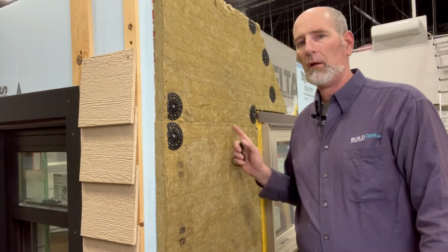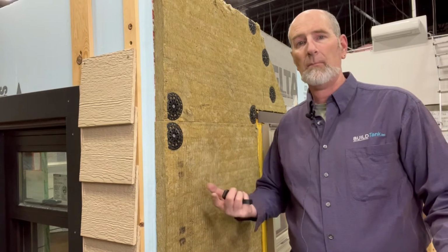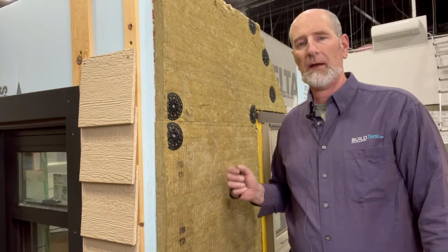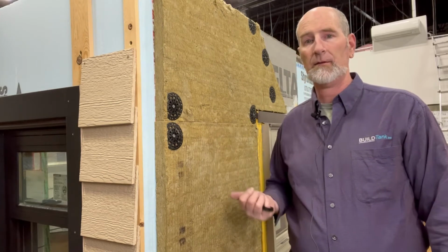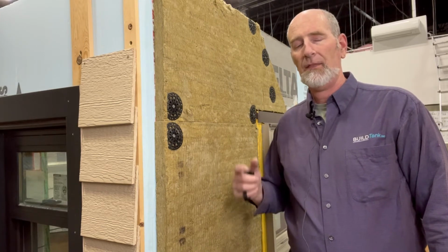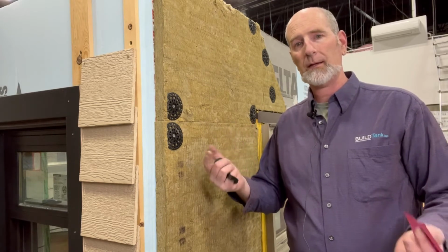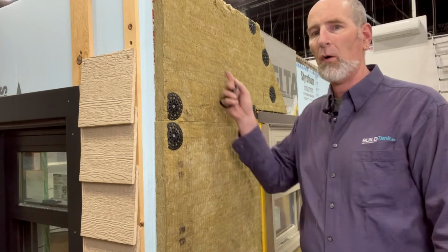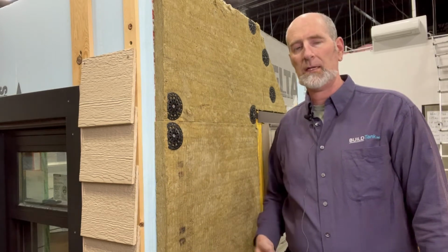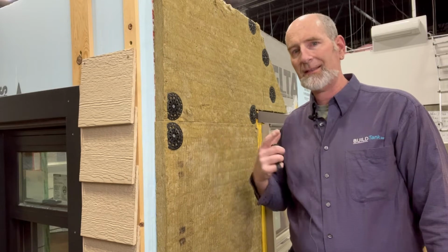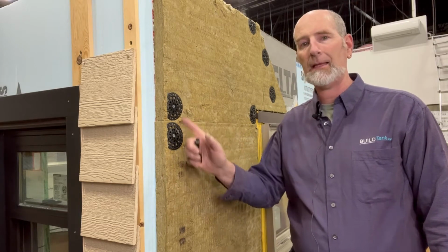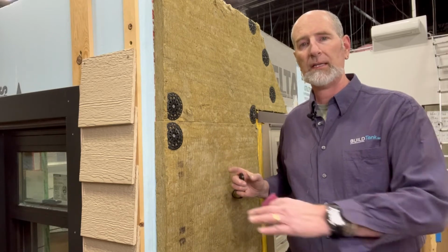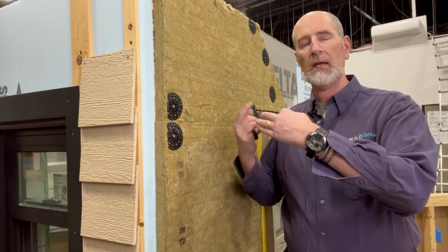Now, the whole wall R value, when I say that I'm building a house with R20 walls, we're really just talking about the cavity behind this here, the cavity insulation. That batt or that blown product that's in that cavity will give me an R value of 20, but that doesn't mean that this whole wall's R value is equal to 20. It means that just at that point inside the cavity, when I add in the framing and I do an area weighted U value calculation, it brings down the total wall R value substantially.